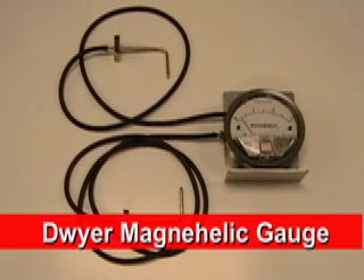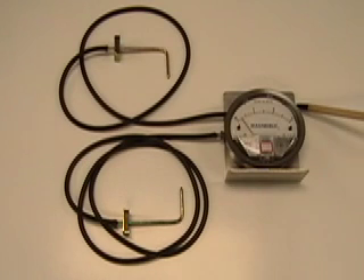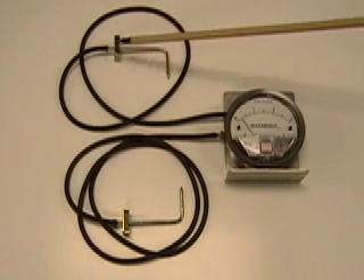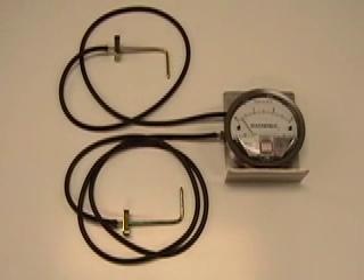All a technician needs to accurately measure airflow is a Magnehelic gauge and two static pressure probes. All of these are made by Dwyer Company and are readily available. The static pressure probes are very handy in that they have a magnetic base, so simply drill a hole in your ductwork for the probe to fit through. The magnet will suck it right up to the ductwork, sealing it off and giving you accurate readings.